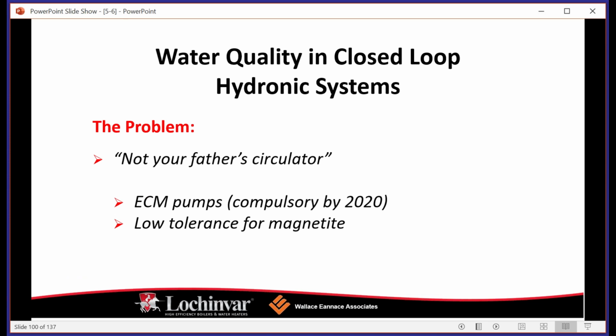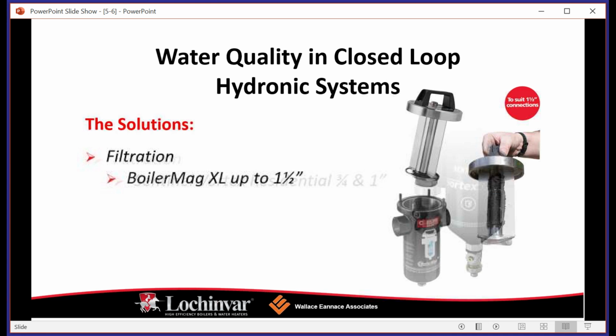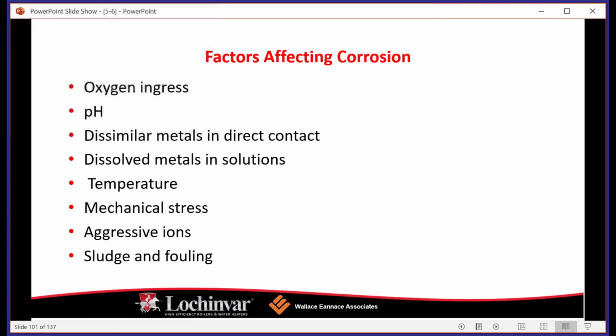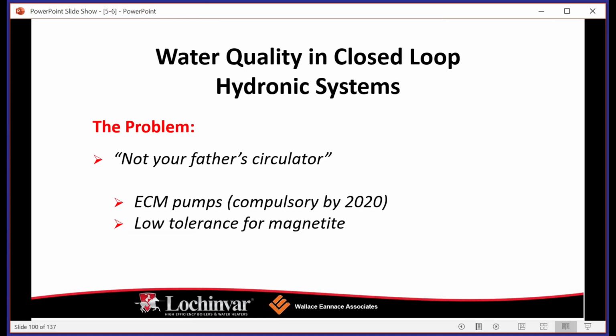Okay, so I just finished talking about water quality and closed loop hydronic systems. And again, it's a closed loop for a boiler. For a water heater, obviously we're taking water in from the street, we're heating it, we're sending it out to our building through our faucets and fixtures. But for a boiler, we're going to install our boiler, we're going to fill the system full of water, and then barring any construction where we have to open up the system, or leaks, the closed loop should have the water in it from the day that it was born.